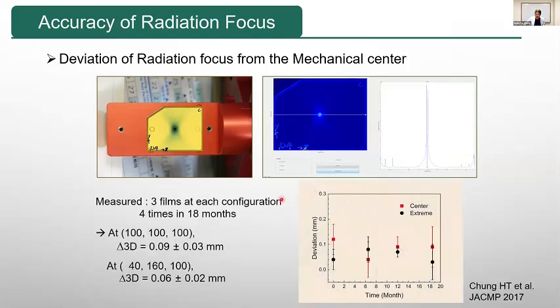I checked this many times. At the center of the coordinate system, 100, 100, 100, the three-dimensional error was 0.09 millimeters. And when we move the couch to an extreme position, 40, 160, the three-dimensional error was 0.06 millimeters. This is very accurate. We can say it is a very accurate machine. The patient couch moves in a very accurate way. This graph shows the measurement results for this radiation focus accuracy. We can see they keep within 0.1 millimeter level for 1.5 years.